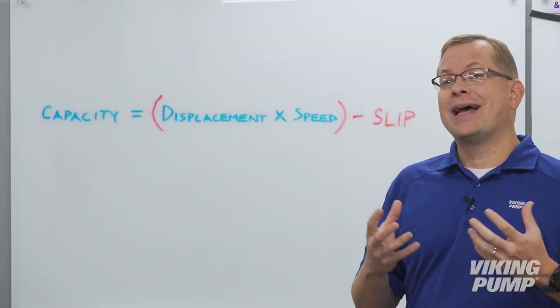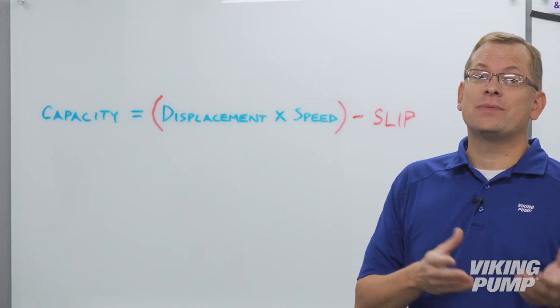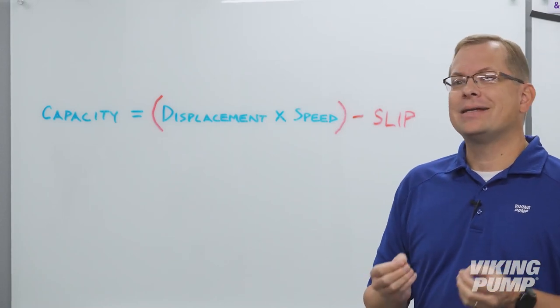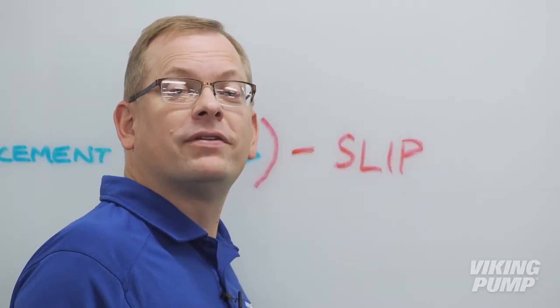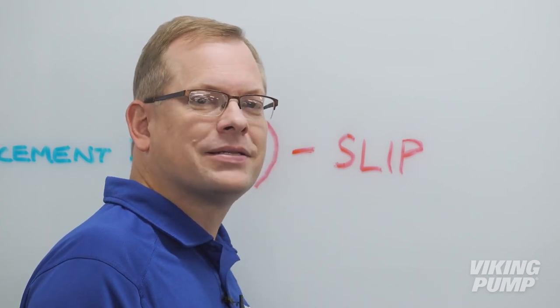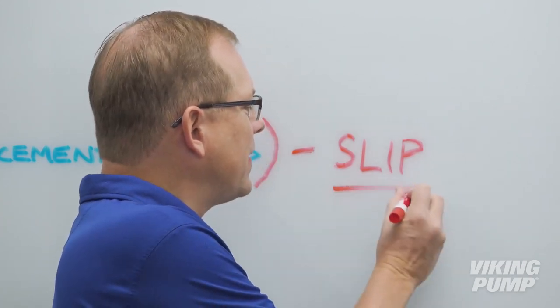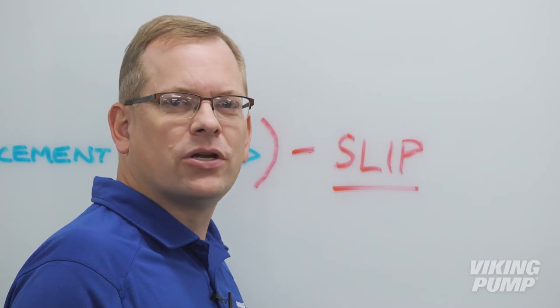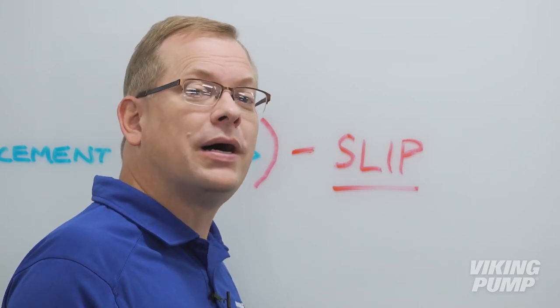So a PD pump's actual capacity will be displacement times speed minus slip. Okay, so I've defined slip, and I've told you how it affects a pump's capacity. But how do we determine this value? How much slip is in your pump, and how much slip is too much?